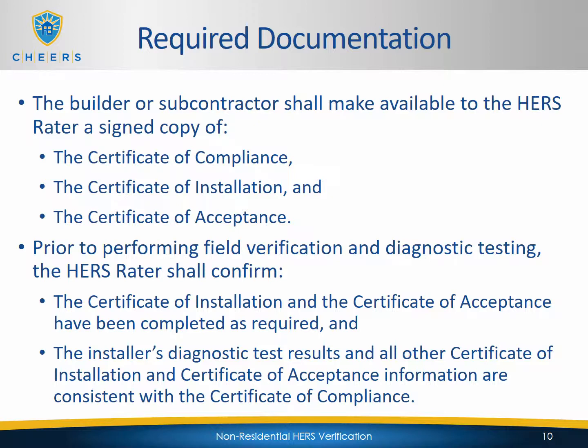Because those other documents are not available in the registry, the builder or subcontractor will need to make copies available to you of the certificate of compliance, certificate of installation, and certificate of acceptance. You need those documents prior to performing your field verification and diagnostic testing. You'll want to confirm that the certificate of installation and certificate of acceptance have been completed as required and that the installer's diagnostic test results are consistent with the certificate of compliance.